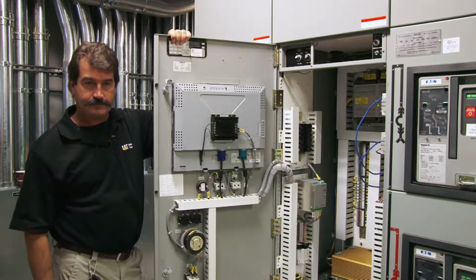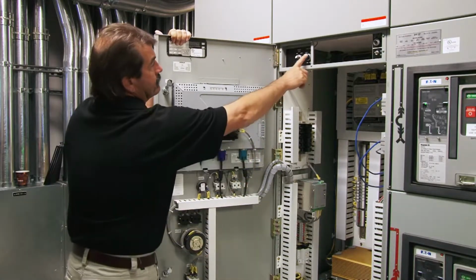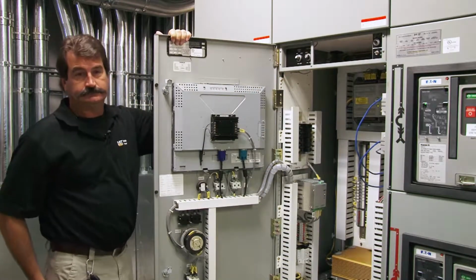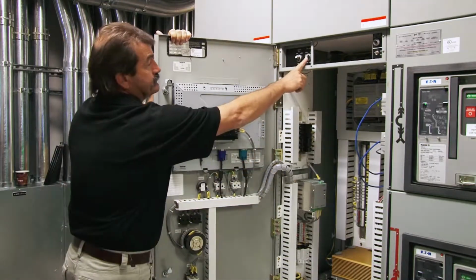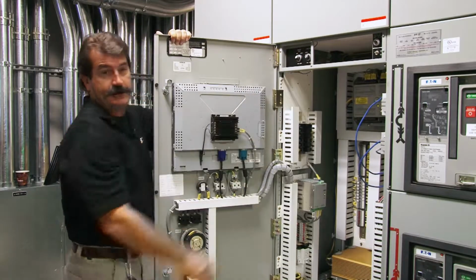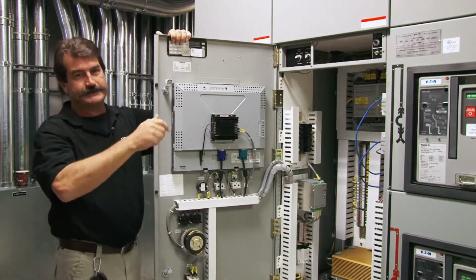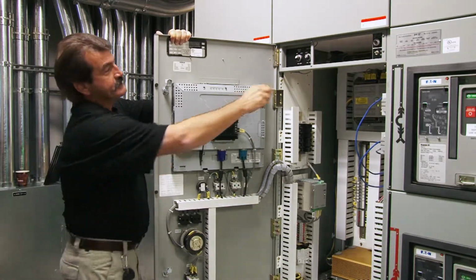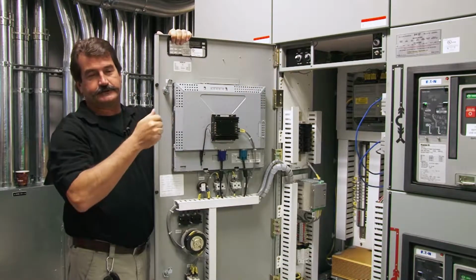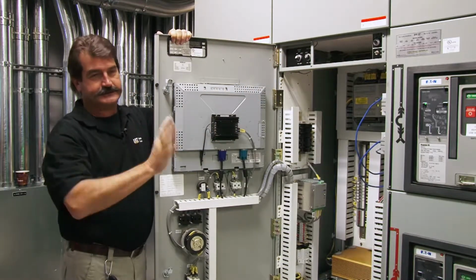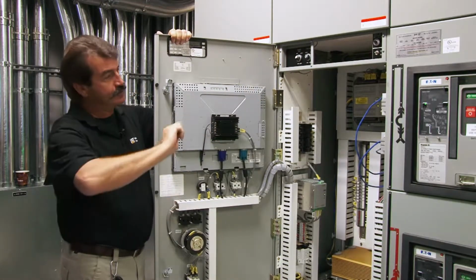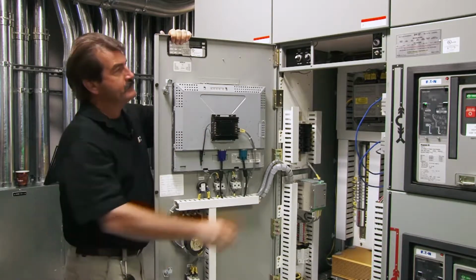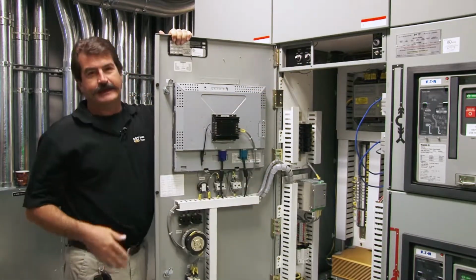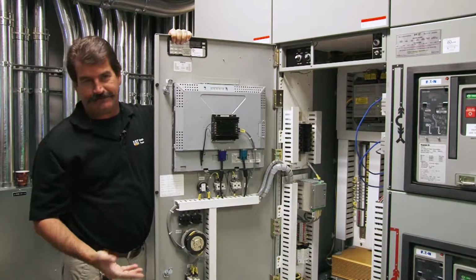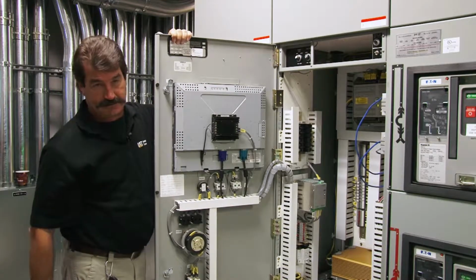Is that an override key right there? Does it require a key? Yes, it does. You've got to have a key in there before you can use it. You need a key for Load Shed, but you do not need a key for Instant Auto. We don't want that, because Instant Auto puts your system in a safe situation, so we want it easily accessible. Load Shed puts your system in a potentially unsafe situation, so we want a key switch for that.